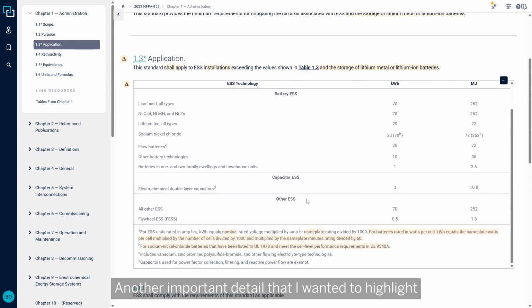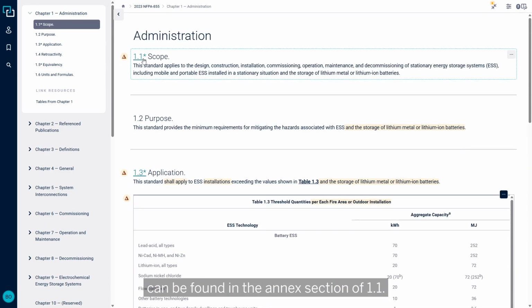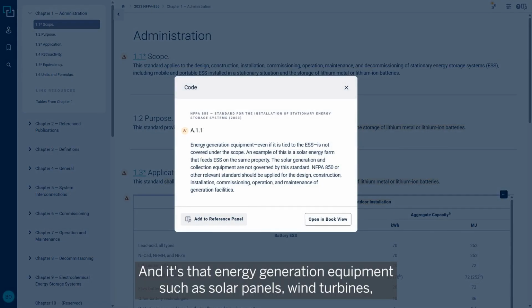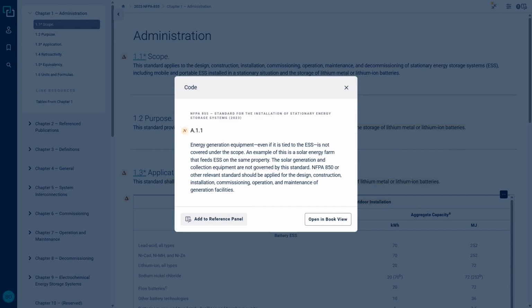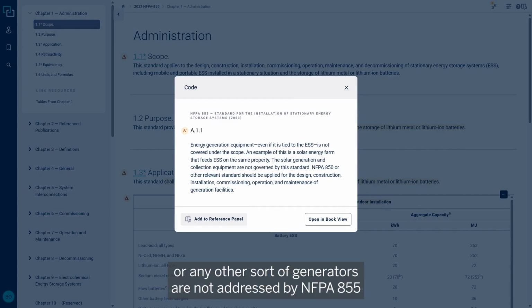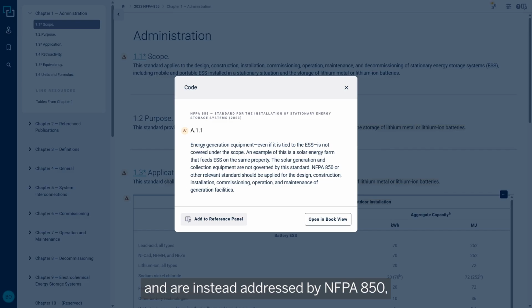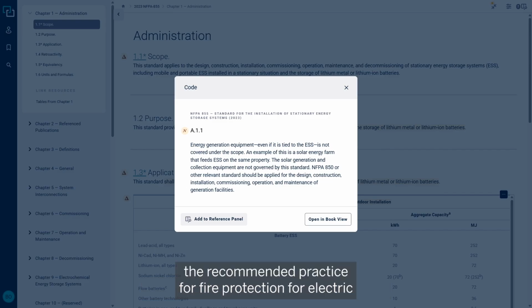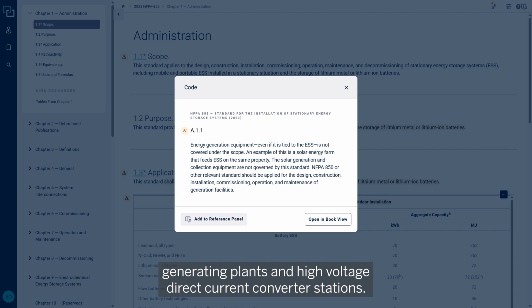Another important detail can be found in the Annex section of 1.1: energy generation equipment, such as solar panels, wind turbines, or other generators, are not addressed by NFPA 855. They're instead addressed by NFPA 850, the recommended practice for fire protection for electric generating plants and high voltage direct current converter stations.